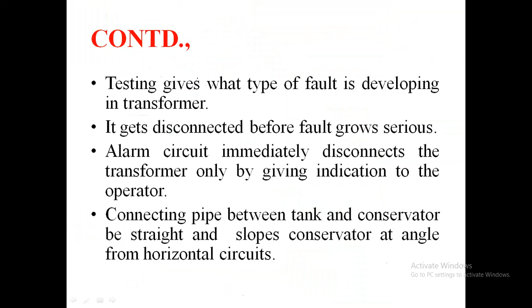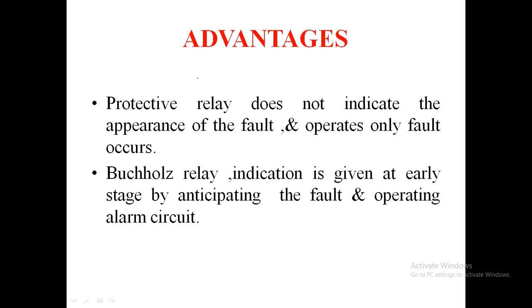Some advantages of this type of relay: it operates only when a fault occurs, and an indication is given at an early stage by anticipating the fault and operating an alarm circuit. And it is a simple protection in the case of a transformer. The applications of this type of relay: local overheating, entrance of air bubbles in the oil, core bolt insulation failure, bushing puncture, winding short circuit, winding earth fault, short circuit between the phases. So these are some of the applications.